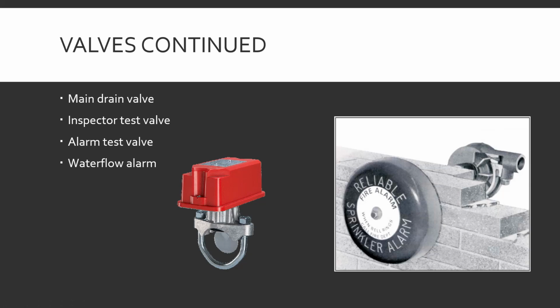Normally it's closed. When they want to test the alarm, they open it. That lets water flow through the system, and it makes the fire alarm system think, I'm flowing water. I have to sound the alarm because there's water flowing. Basically, fooling the system into thinking that a sprinkler is open or what have you, to test how the alarm system works, if everything's working correctly.